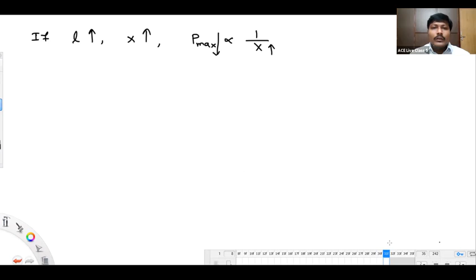So let's see. If length of transmission line was getting increased, what will happen? That's a study we are going to take up in a simple way. If the length of transmission line is increased, definitely the series reactance of the line is going to increase. X value is going to be increased. So what will happen to maximum power transfer capacity? You know, this maximum power transfer capacity is inversely proportional to reactance. So as reactance is increasing, Pmax value will decrease. Now, as you know, P equals Pmax into sine delta.